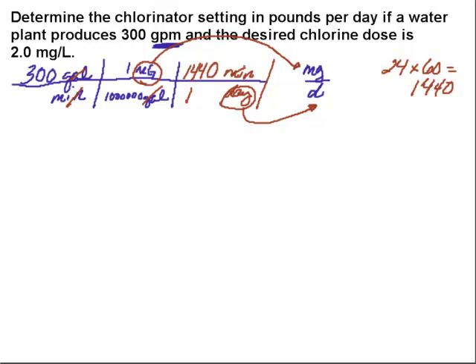So I'm going to plug that into my calculator. 300 times 1440 divided by a million, and make sure that you get those six zeros in there. I always like to punch this one in twice, and what I end up with is 0.432 million gallons per day for this plant.